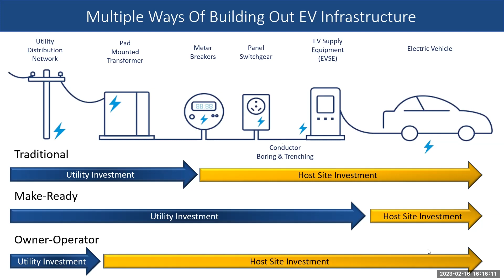So that integrated module - we came up with the concept called E2V, an integrated power module, which essentially consists of medium voltage breakers, a dry transformer, a main breaker panel, and low voltage distribution, all into one single unit. If you look at the traditional site, we are removing the transformer, the voltage breaker, the metering, and also the boring and trenching and everything else that goes along with it. Essentially, you end up with a solution that's pretty much plug and play, condensing that total infrastructure into a much smaller footprint.